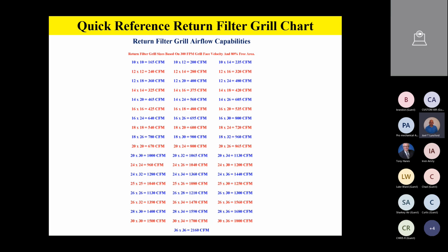So we wanted to provide this to you as well. These have already been figured out for you. And so if you've got a 24 by 24 grill, you look on here and say, well, gee, a 24 by 24 is good for about 960 CFM based on Manual D recommendations of 300 feet a minute maximum grill face velocity and 80% free area. So I just wanted to kind of equip everybody with this. This is just a little quick reference guide that'll help you size filter grills at a glance. So any questions or comments on this little quick reference guide we provided to you as well?